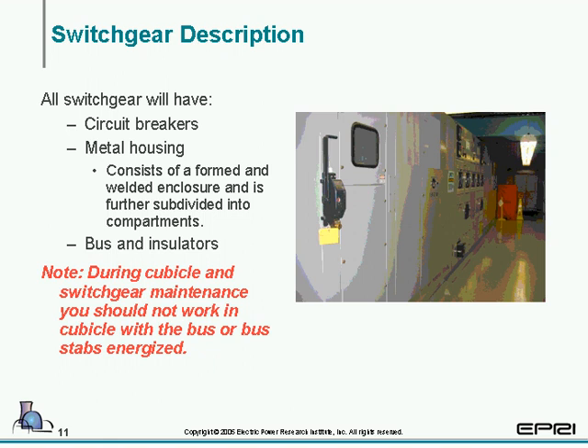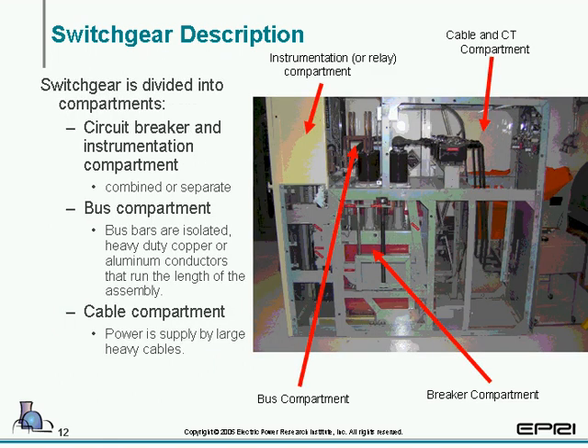All switchgear has circuit breakers, a metal housing, bus, and insulation, or insulators. Note, during cubicle and switchgear maintenance, you should not work in cubicles with bus or bus stabs energized. And here we have a single cubicle switchgear that is divided into its compartments. First one we have is a circuit breaker and instrumentation, and that typically would be in the front. Then we have the bus compartment.